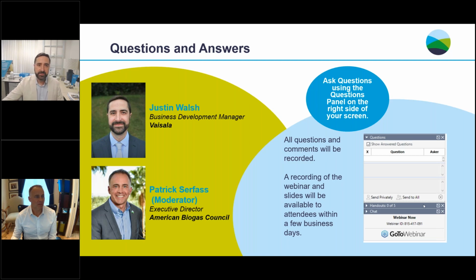But if you're calibrating in the field, you can do that yourself with locally sourced calibration gases. The likelihood that a lot of these facilities are using calibration gases for other instrumentation is pretty high, so you can either use what you're purchasing for somebody else, or purchase your own mix. We do have some guidelines in the manual, but they're loose, so you can really use whatever is appropriate for your application. And we do sell that flow-through chamber. It's currently just shy of $500, but it really is just an inlet and an outlet, and you could make something yourself if you wanted to.